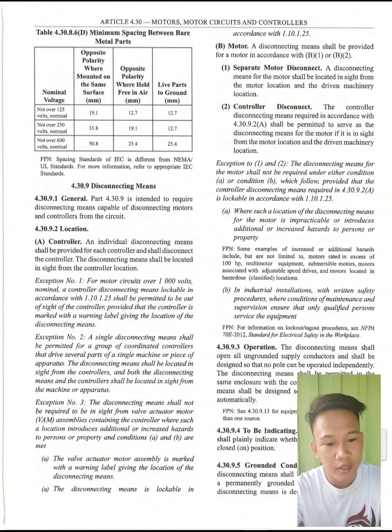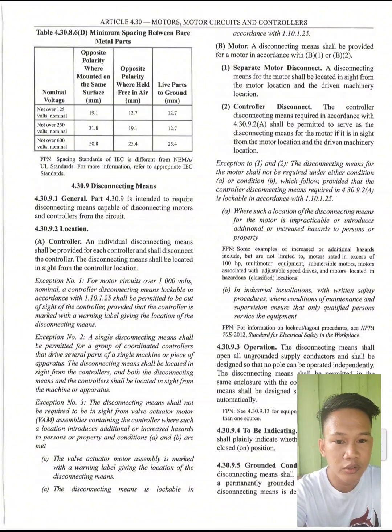So next is 4.30.9.3 operation. The disconnecting means shall open all ungrounded supply conductors and shall be designed so that no pole can be operated independently. The disconnecting means shall be permitted in the same enclosure with the controller. The disconnecting means shall be designed so that it cannot be closed automatically. Next is 4.30.9.4 to be indicating. The disconnecting means shall plainly indicate whether it is in the open or off, or closed or on position.